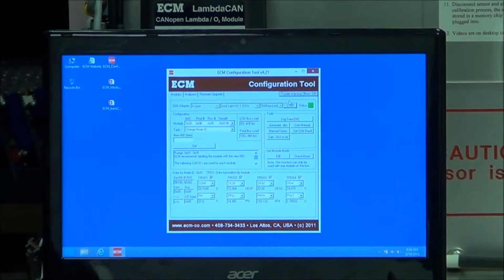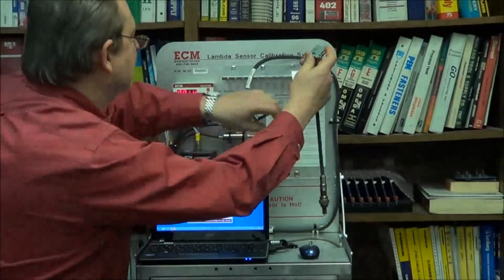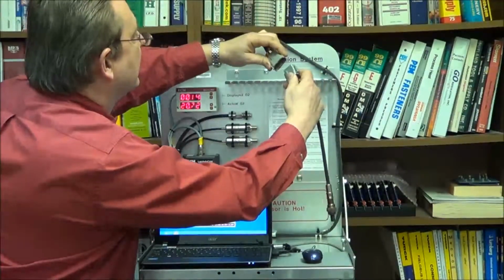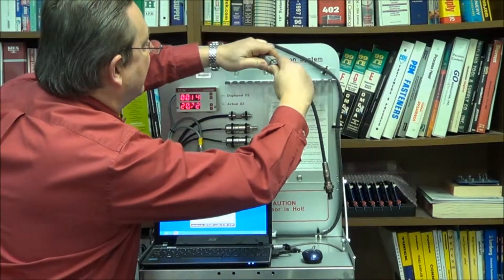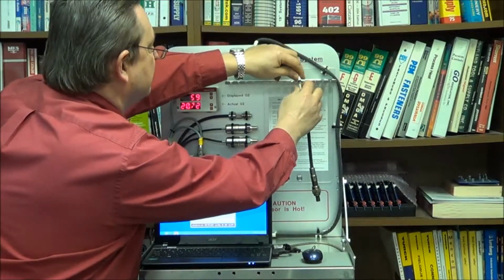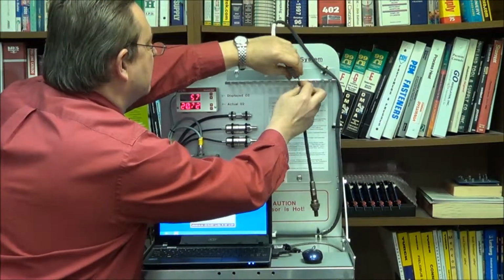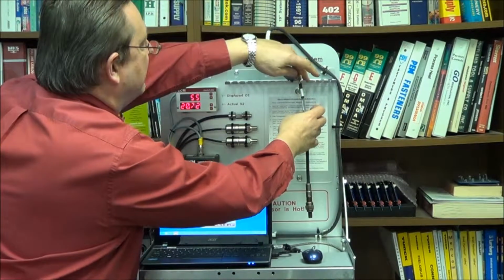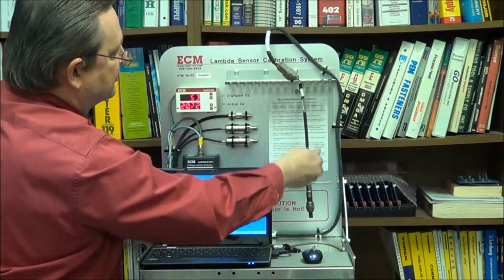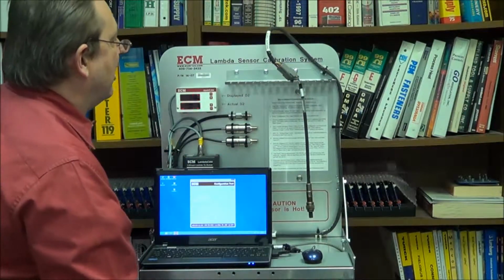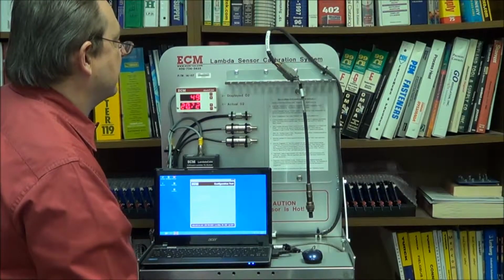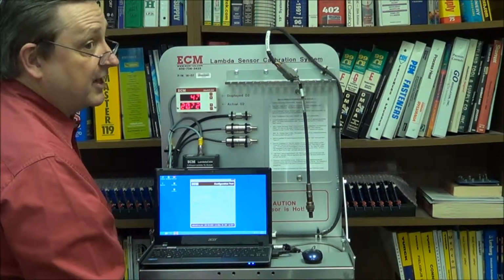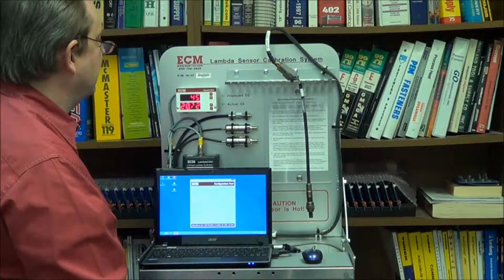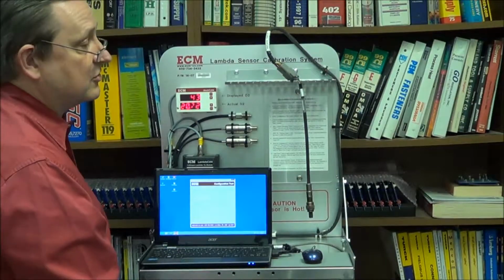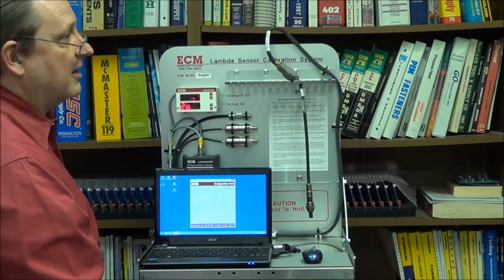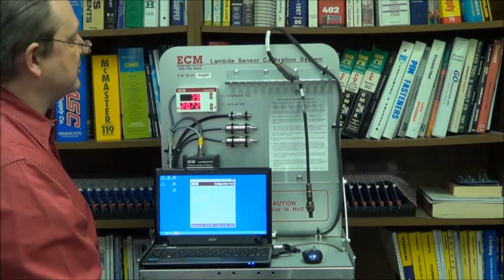Then you connect the sensor to the LambdaCAN cable and hang it in stationary air, your cal gas, pointing down. And this tray with the fingers allows you to put the sensor at different heights. Some sensors have longer cables than others. The sensor is going to get hot, so be careful. In 1 minute, the sensor will be close to its proper temperature.